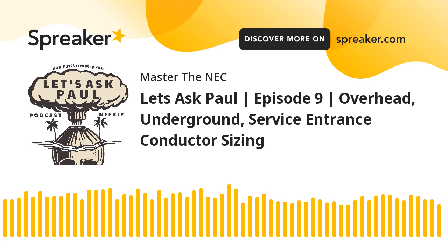You've got all these things, but when it comes to the grounded conductor, in many cases it will be a neutral. A grounded conductor is always the case when it's a grounded system, but a neutral is what we probably would talk about the most when it comes to single family dwellings, multifamily dwellings, things like that. 120/240 volt grounded loads. You can also have 120/208 grounded systems. When you're sizing the grounded neutral, in that case, you have to size it based on Part 3 of Article 220, because the method to do this is not over in Part 4 for the optional method. It is in Part 3.